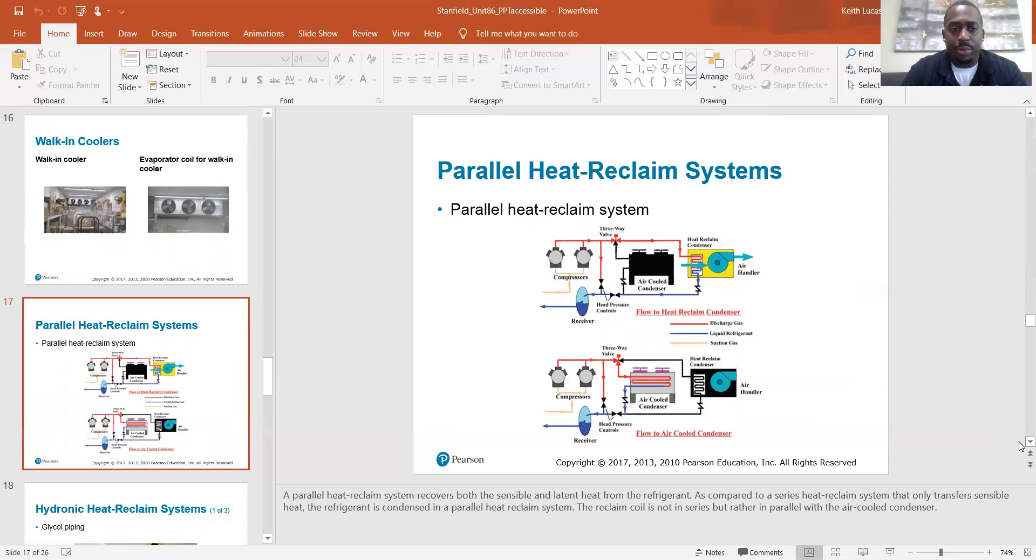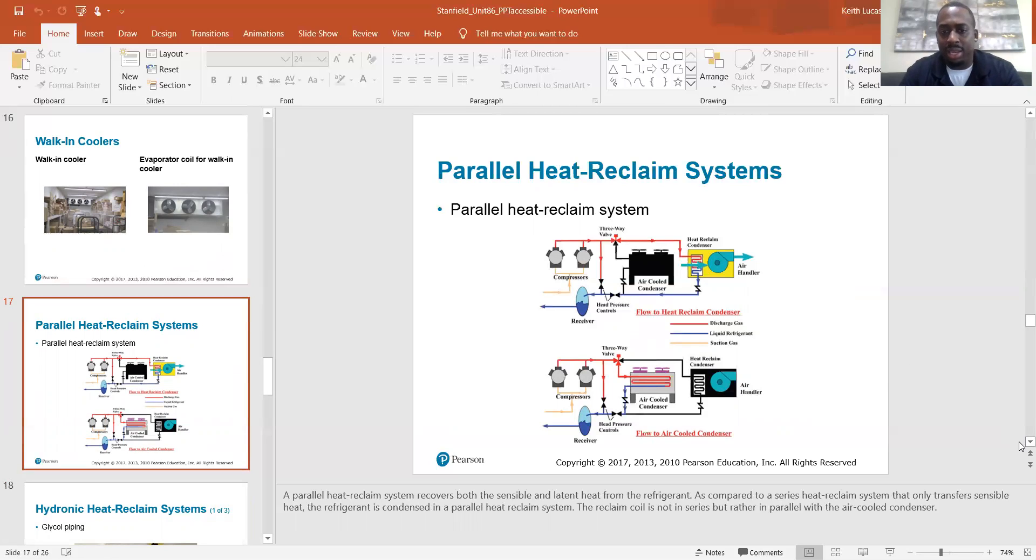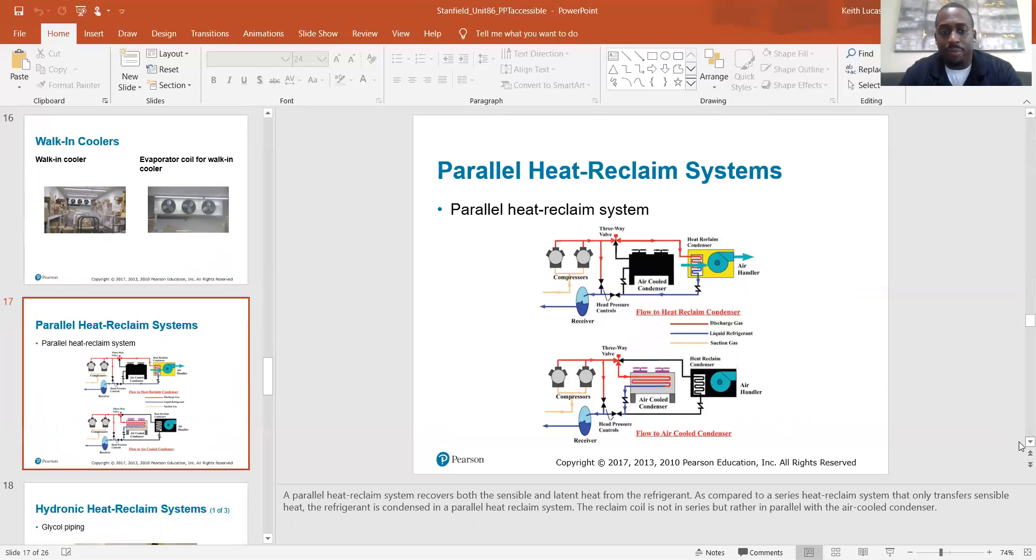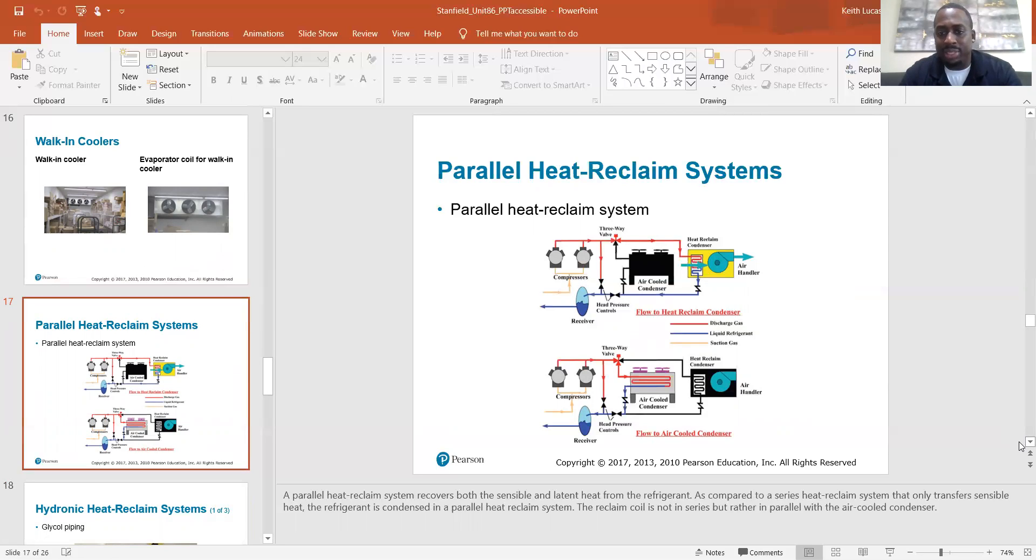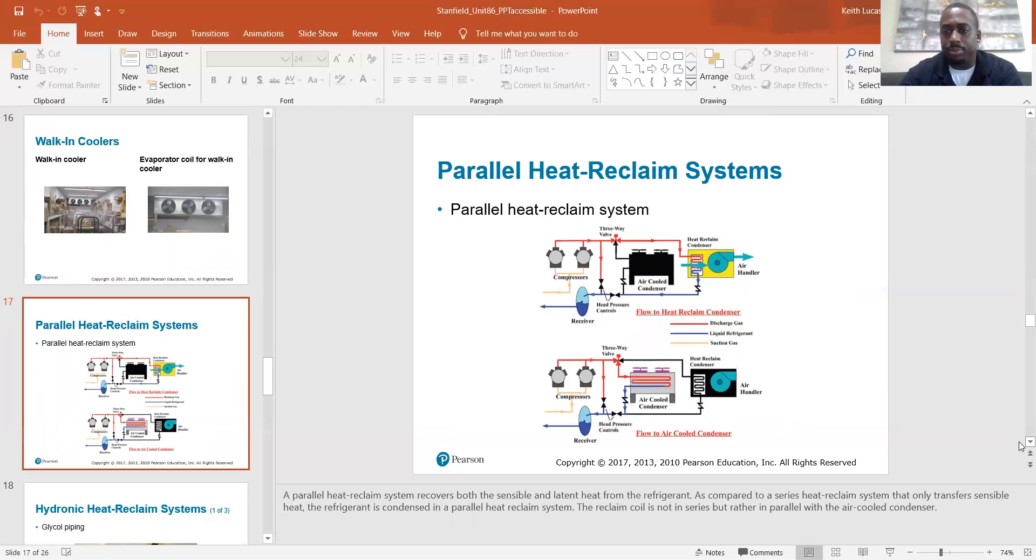Parallel heat reclaim systems. A parallel heat reclaim system recovers both the sensible and latent heat from the refrigerant. As compared to a series heat reclaim system that only transfers sensible heat, the refrigerant is condensed in a parallel heat reclaim system. The reclaimed coil is not in series, but rather in parallel with the air-cooled condenser.